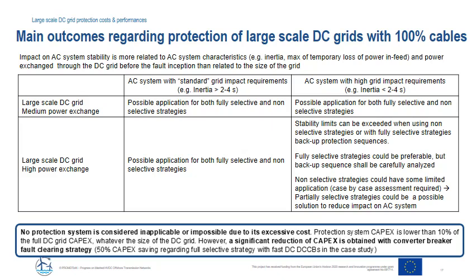The case of a large-scale DC grid exchanging high power with an AC system with high grid impact requirement requires particular attention. In such a case, stability limits can be exceeded when using non-selective strategies or with fully selective strategies' backup protection sequences. Fully selective strategies could then be preferable, but the backup protection sequence should be carefully analyzed. Non-selective strategies could have some limited application, but a case-by-case assessment would be required to fully conclude.